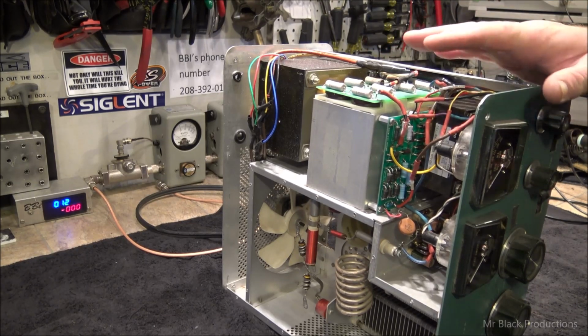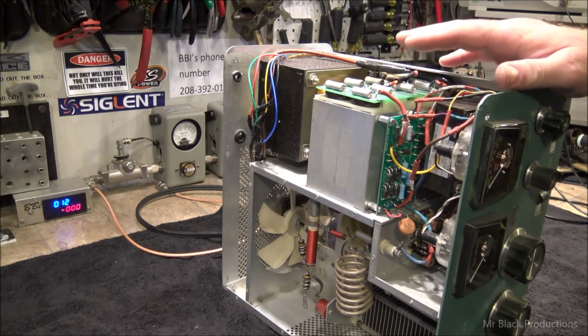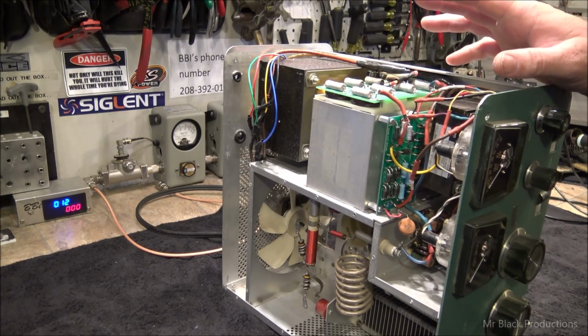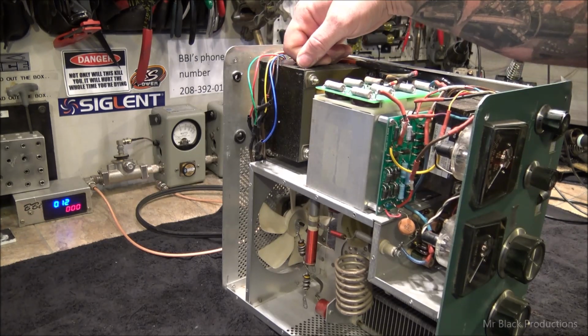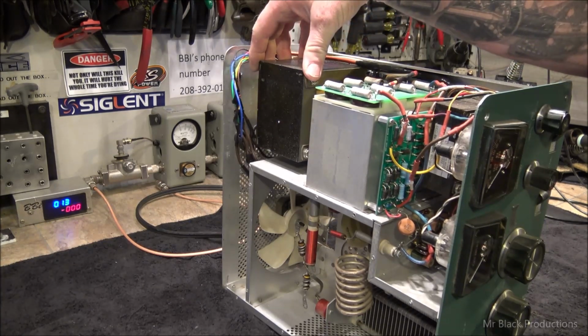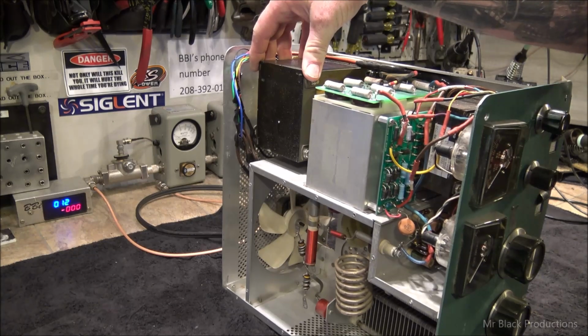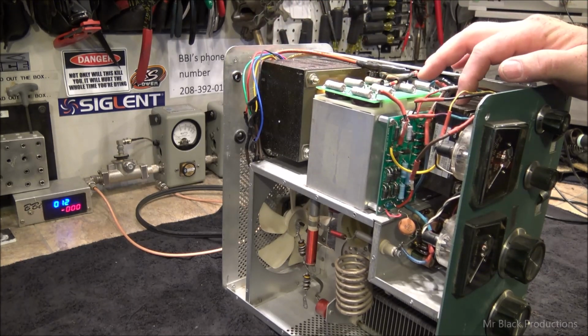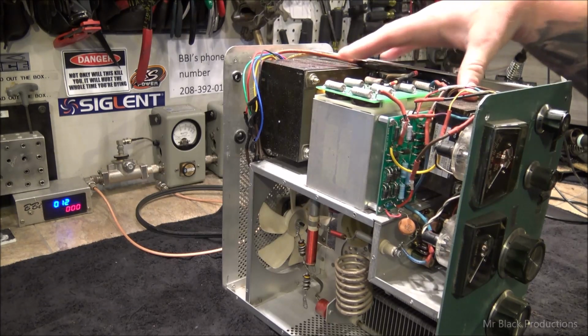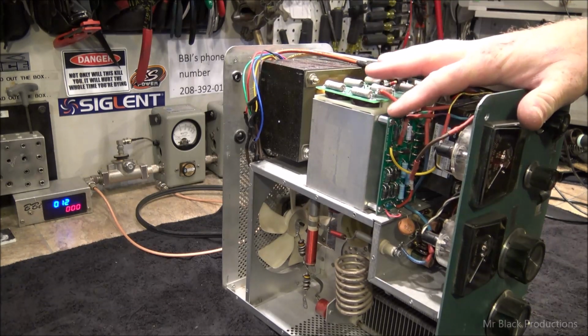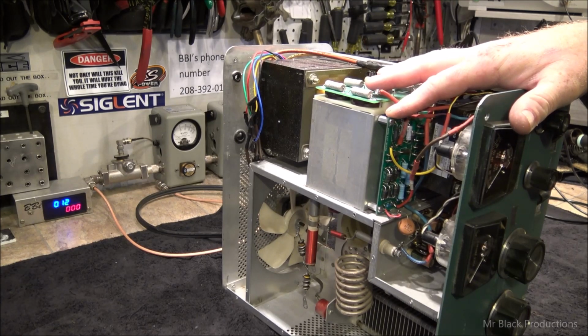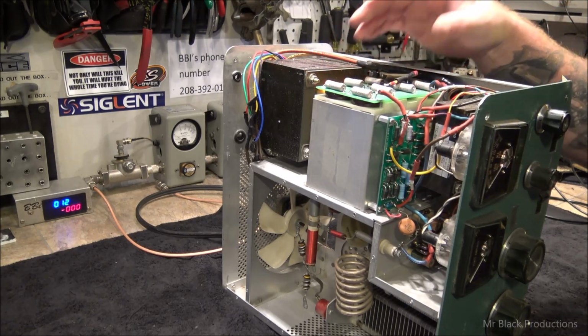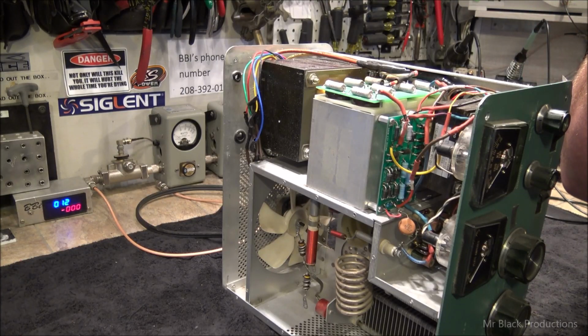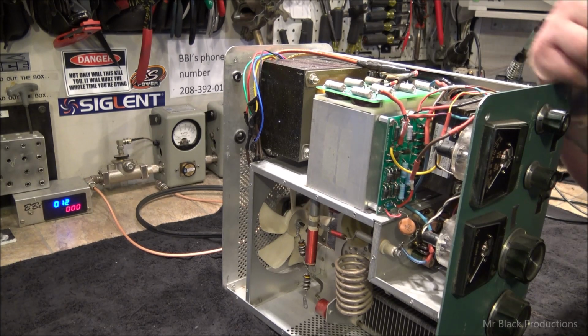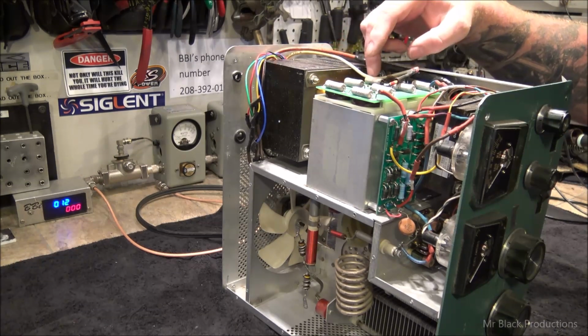Okay, so the primary issue that this gentleman has is he said that he turned it on. First he tried to do, this is the EPD, electronic product design, replacement transformer right here. Then over here is the EPD electronic product design replacement filament transformer. Both of these are good solid products. Then he replaced the high voltage board with the Harbach board, and then he replaced the capacitor bank with the Harbach board. But how it was done was not safe by any means.